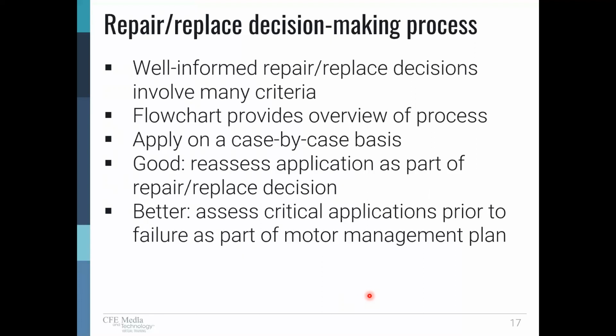If it's a drip-proof motor, an open motor, and it's being used in a harsh environment, like maybe outside, subject to snow and wind and rain and so forth and dust, maybe we want to look at the possibility of not repairing that motor and changing it out, replacing it with a totally enclosed fan-cooled motor. A better approach, even beyond that, taking the next step, if you will, is assessing the critical applications prior to failure. Let's say we had a facility and we had 3 truly critical motors. Without any one of those 3 motors, the whole plant goes down. Well, those are the motors that we don't want to wait for the day when they fail to come in and say, we need to get a plan together. The idea is to have that pre-planned and say, if motor A goes down, here's what we're going to do. We're going to have a spare, or we know another plant that has a spare motor, we'll get it from them. Or we're going to tell the service center, work around the clock and get this thing fixed as fast as possible. We want that repair, don't hold up on anything, keep it going around the clock.